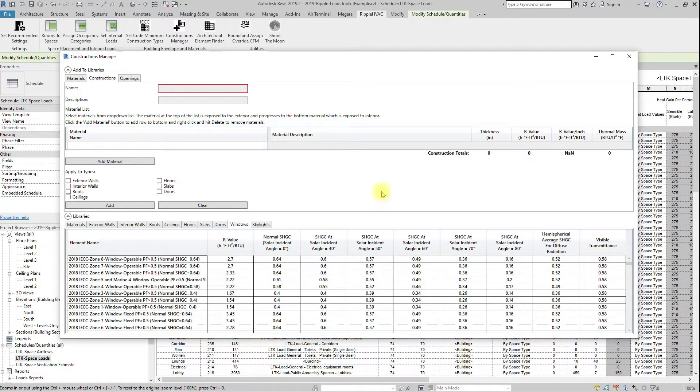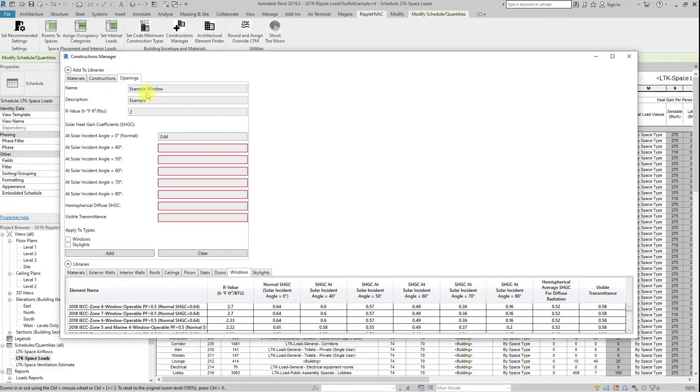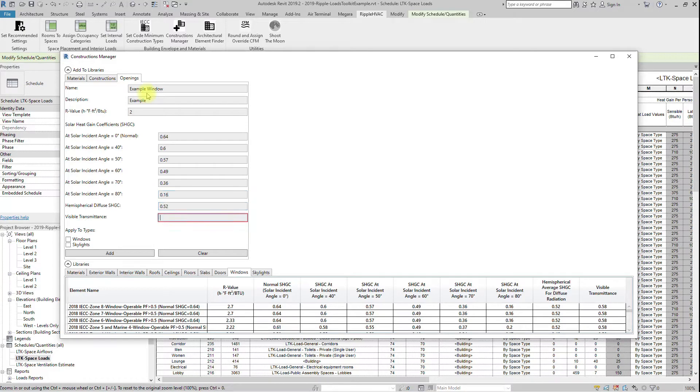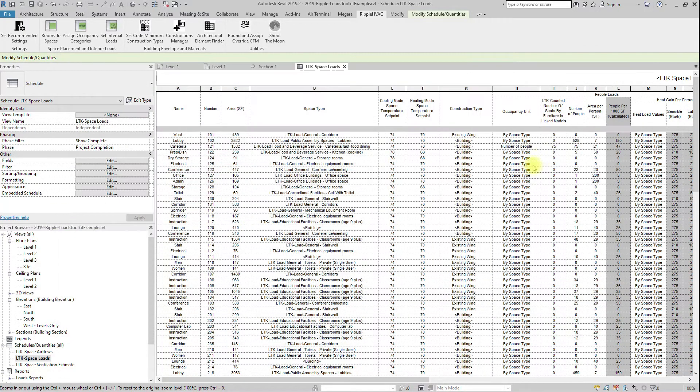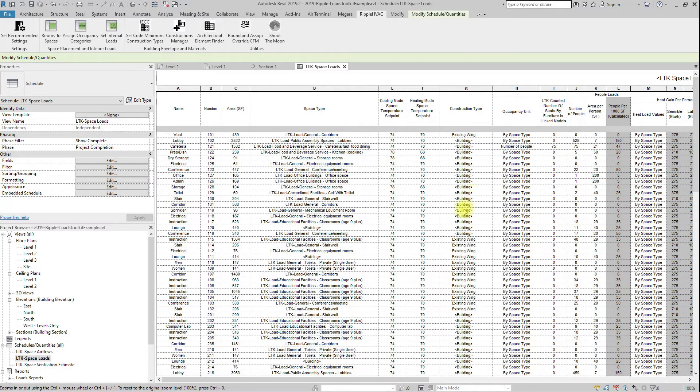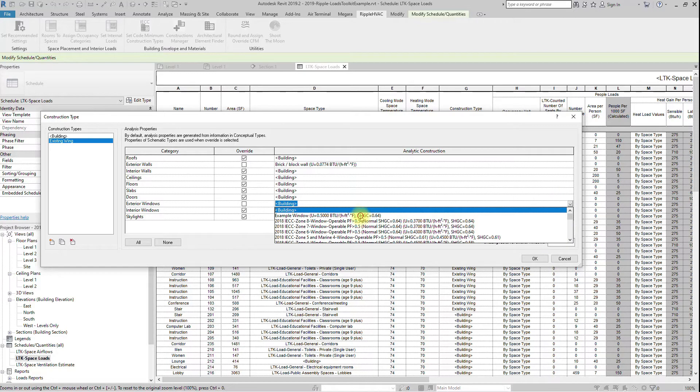The windows and skylights are defined by an R value, solar heat gain coefficients at different angles, and visible transmittance. Enter these values, check the types, and click Add. Your new custom constructions will now be available in the construction types dialog.